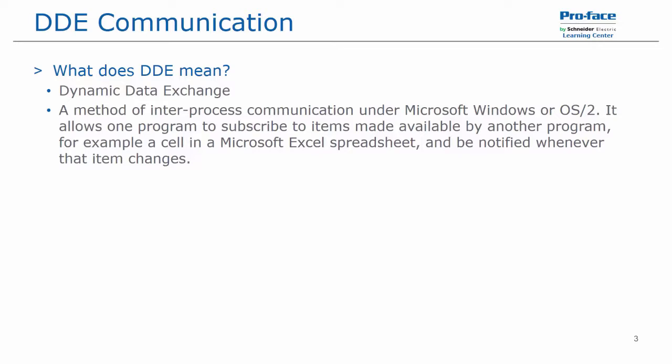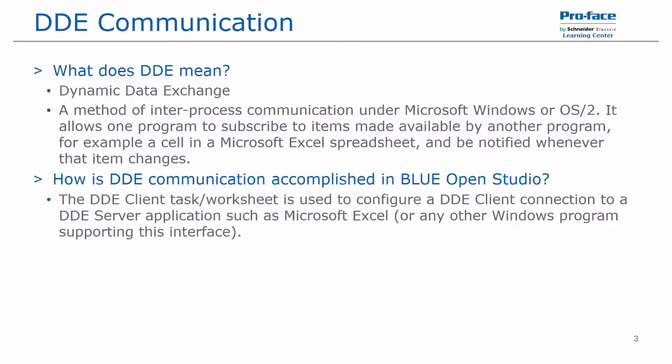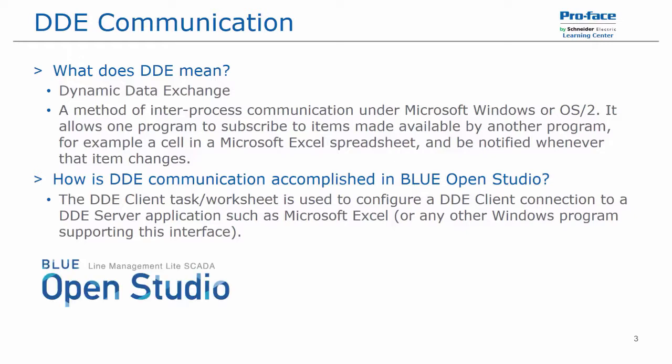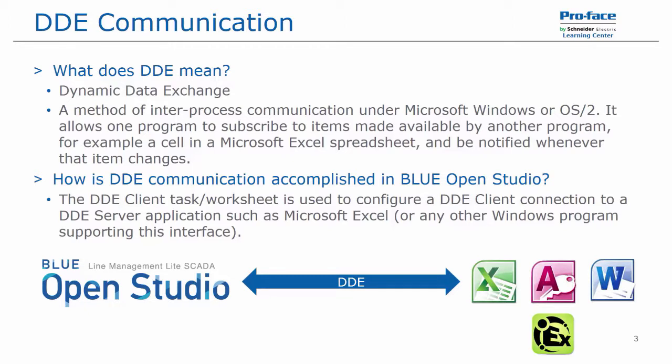Via DDE communication, that program can be notified whenever that item changes value. How we accomplish DDE communication in Blue OpenStudio is we use a client task or worksheet to configure a DDE client to connect to a DDE server application such as Microsoft Excel or any other Windows program that supports this interface. We can communicate to numerous Windows applications including Excel, Access, Word, and even some SCADA systems like KepServerEx.